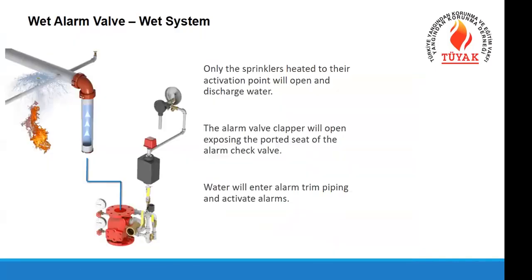This is basically a wet alarm valve. It works as an alarm device — it gives an alarm. There is a water motor alarm, like a gong, that turns with water velocity and gives an alarm mechanically, ringing like a bell to alert people in the building to escape and guide the fire brigade to the right location. We also have an electrical alarm device: when water flows, the electrical alarm is sent to the fire detection panel, giving a secondary electrical alarm signal.